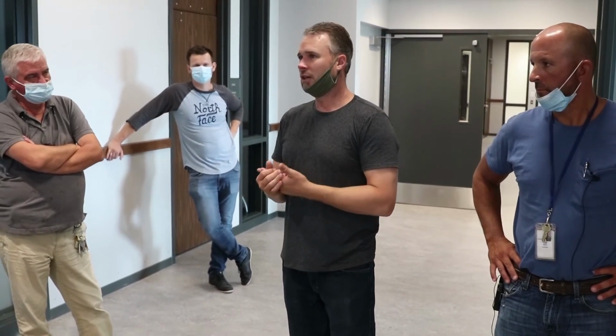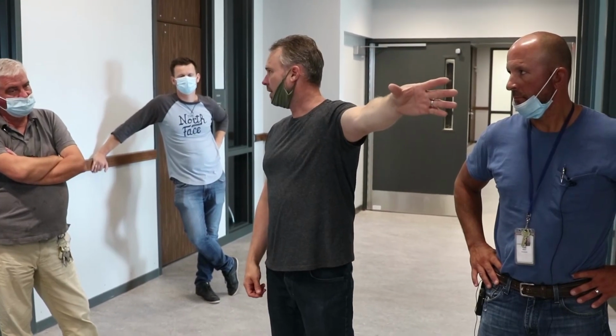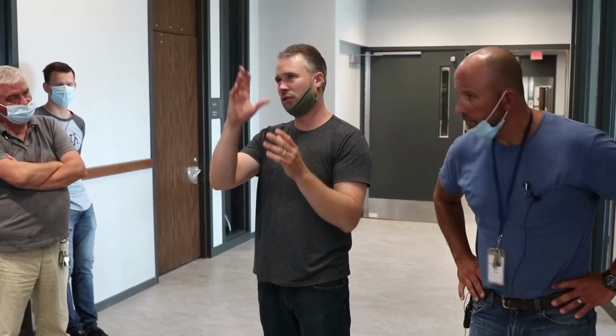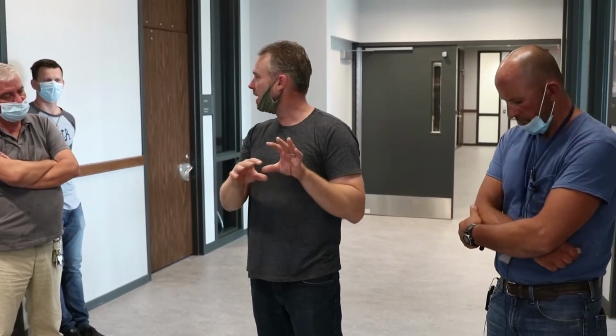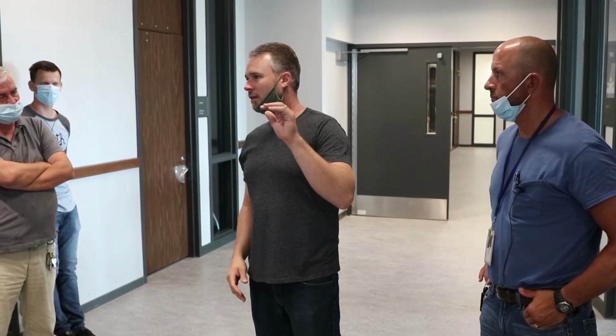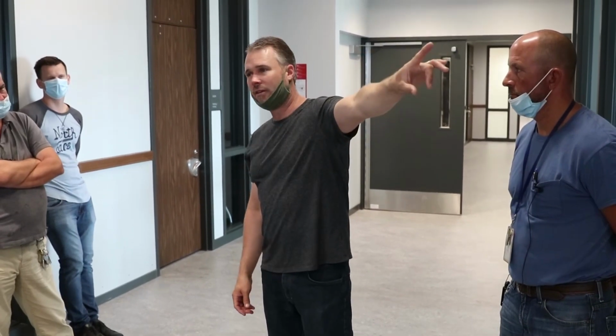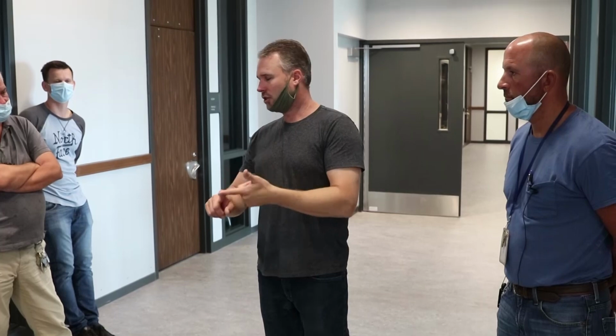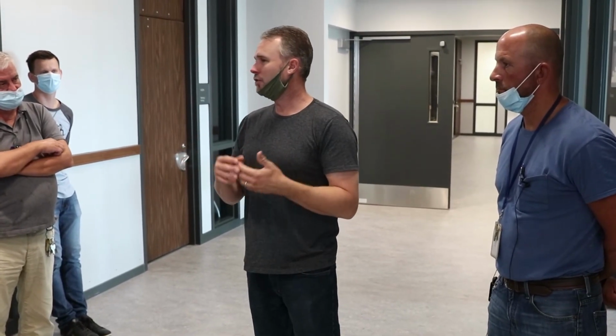So you have TX fans, which are toilet exhaust fans, and GX fans, which are general exhaust fans. The general exhaust fans include things like laundry. Looking down this corridor, there's a laundry room over here with 2 separate exhaust fans: a general exhaust fan that serves the laundry room itself, with a grill exhausting the room, and a fan connected to the dryers. Those dryer fans operate on their own based on demand, modulating based on how many dryers are running. There's a static pressure sensor in the ducts down here that controls those fans. So TX is toilet exhaust, GX is general exhaust, used for laundry, salons, and similar spaces.